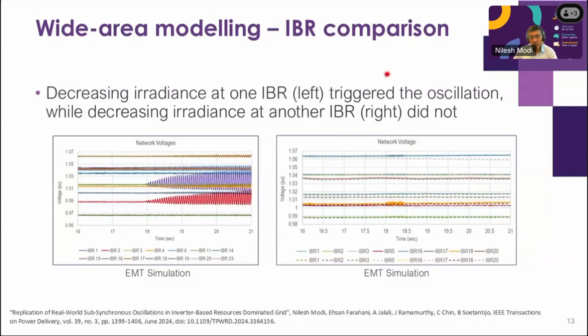Going a little bit further, on the left hand side you can see the West Murray area voltages at those buses, and this is where you see the presence of oscillation. They are within the West Murray area, and the buses where you can see a very small, tiny oscillation are towards the boundary of the West Murray area, and this is aligning with what we observe in real time. So the simulation is matching with real time to a certain extent. When we change the irradiance at other IBRs, there isn't any clear oscillation in the simulation modeling, which again tells us that there is one IBR which could be causing this oscillation.